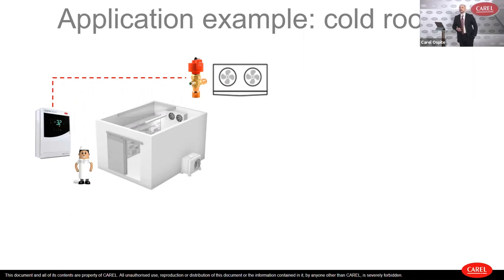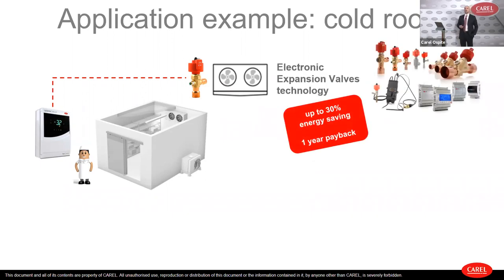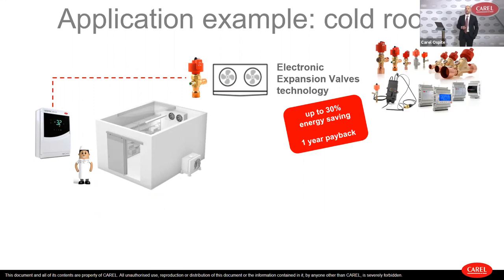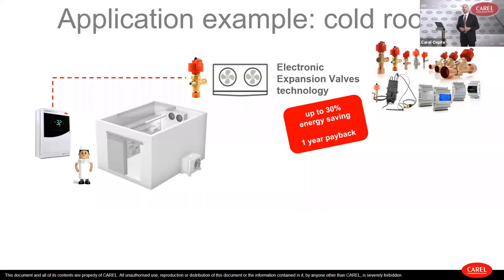Going to the application — we speak about the electronic expansion valve. The AXV system by CAREL can grant up to 30% energy saving on a cold room, for example, and around one year of payback. Electronic expansion valves cost more than a thermostatic mechanical valve, but the energy saved by using this technology can be recovered in around one year, and then for the following years it's all energy and money bill saved.